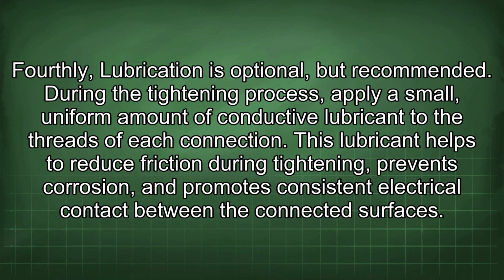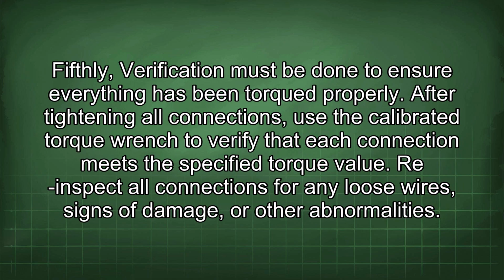Fourthly, lubrication is optional but recommended. During the tightening process, apply a small, uniform amount of conductive lubricant to the threads of each connection. This lubricant helps to reduce friction during tightening, prevents corrosion, and promotes consistent electrical contact between the connected surfaces. Fifthly, verification must be done to ensure everything has been torqued properly.